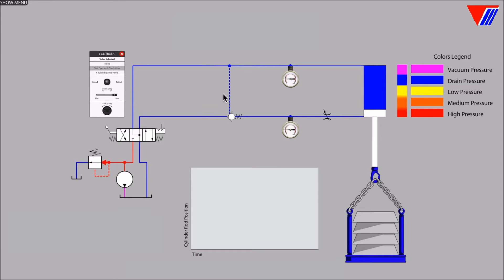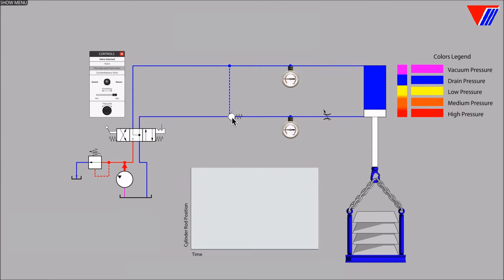There is no flow on this dash pilot line. It is only a pressure signal to a piston inside the check valve that lifts the ball off the seat during that right to left flow.